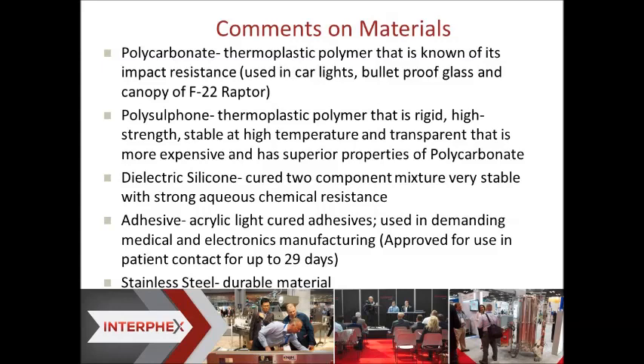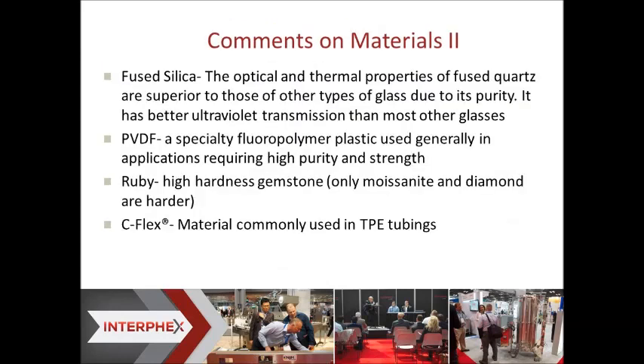The adhesives we use are acrylic light cured adhesives. They're used in demanding medical and electronic manufacturing processes, and they're approved in medical devices for patient contact up to 29 days, and they're also used for components that are used for many years. As everyone knows, stainless steel is a very durable material. Fused silica is very pure glass, and it has better ultraviolet light transmission than most other glasses. And everyone knows glass has some weak points, but it's very durable too.